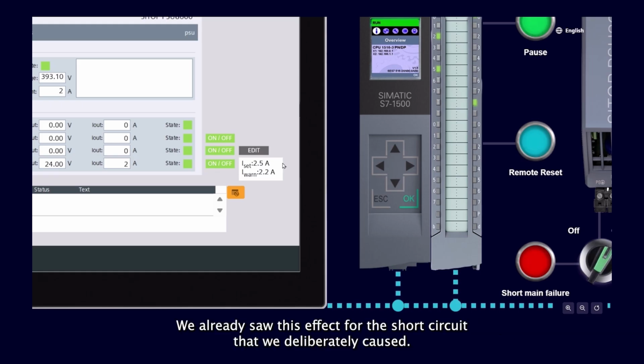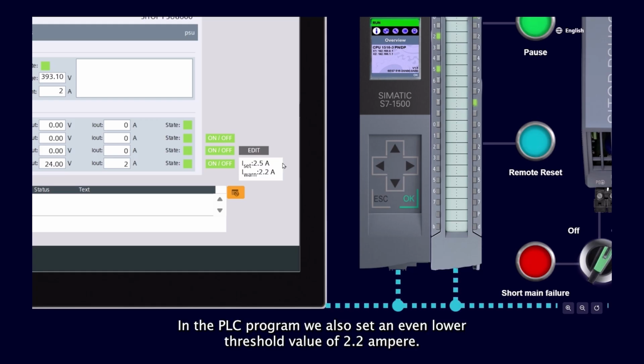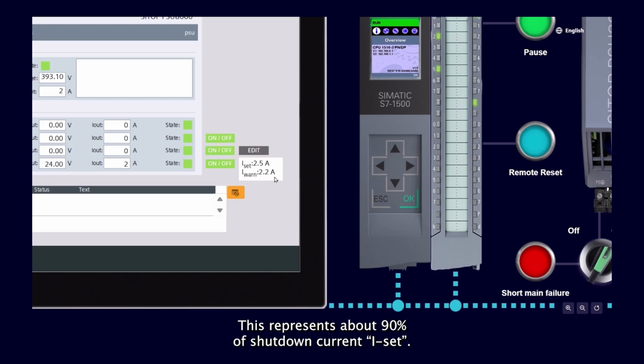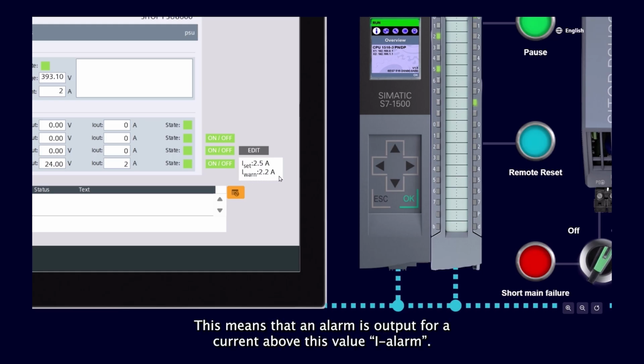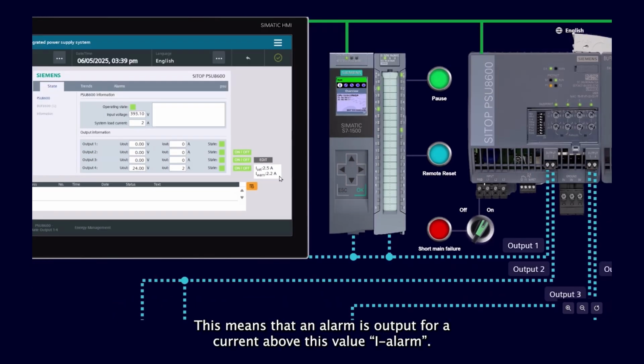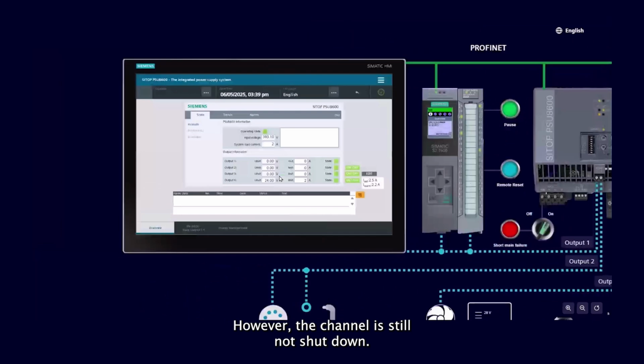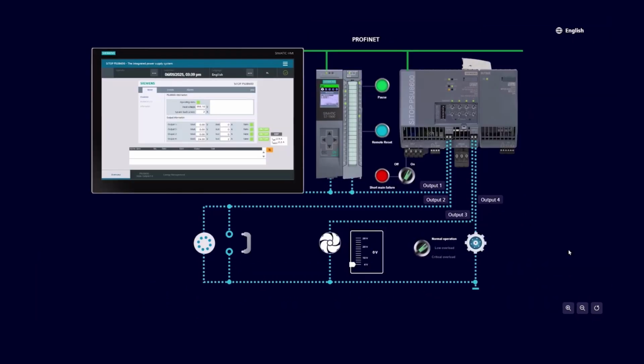We already saw this effect for the short circuit that we deliberately caused. In the PLC program, we also set an even lower threshold value of 2.2 ampere. This represents about 90% of shutdown current I set. This means that an alarm is output for a current above this value, I-alarm. However, the channel is still not shut down.